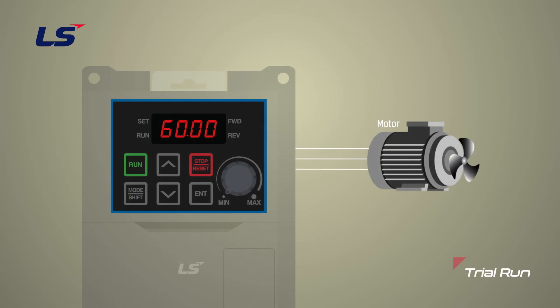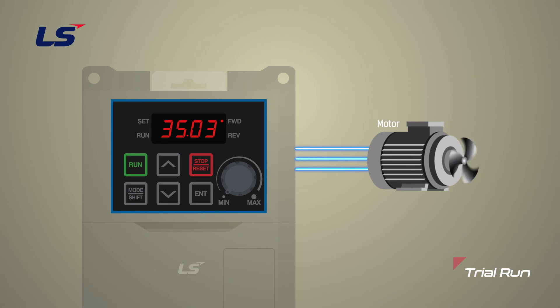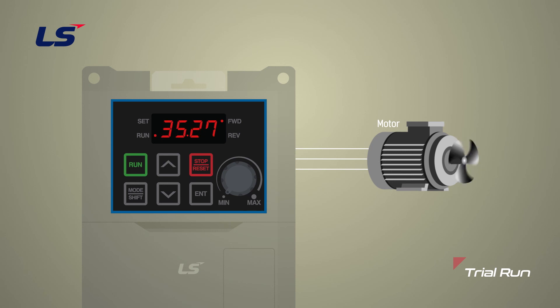Now, let's run the G100. If you press the run key, the forward and run LEDs will light up, and the seven segment window will display the output frequency in Hertz. If you don't change the acceleration mode, it will accelerate according to the acceleration time set by default. So you will reach the maximum frequency and the target frequency of 60 Hertz in just 10 seconds, which is the acceleration time set earlier. To stop, press the stop reset button. If the deceleration time is set to 10 seconds, it will stop in 10 seconds.